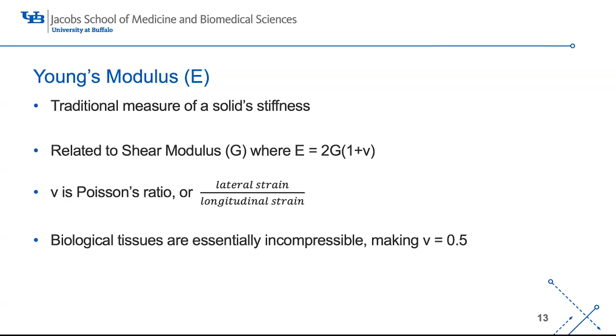So E, the Young's modulus, is equal to 2 times the shear modulus times 1 plus Poisson's ratio, which is little v or nu. Poisson's ratio is the ratio of lateral strain to longitudinal strain on tissue. But the good news is when you're doing elastography, Poisson's ratio is kind of pointless because you make a lot of assumptions in the physics of elastography to produce images that look nice. One of those assumptions is that biological tissues, because they hold so much water, are essentially incompressible. And when tissues are incompressible, it makes the Poisson's ratio 0.5. Plugging it back into this equation, you find that the Young's modulus is just equal to 3 times the shear modulus, or the shear modulus is just 1/3 the Young's modulus. But as I mentioned, both are reported in the literature to give you an idea of tissue stiffness.